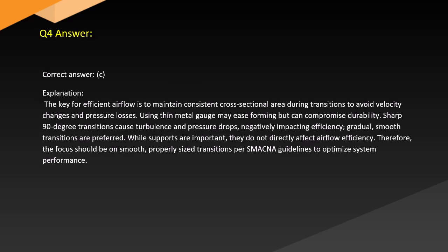Answer. Correct answer: C. Explanation. The key for efficient airflow is to maintain consistent cross-sectional area during transitions to avoid velocity changes and pressure losses. Using thin metal gauge may ease forming but can compromise durability.